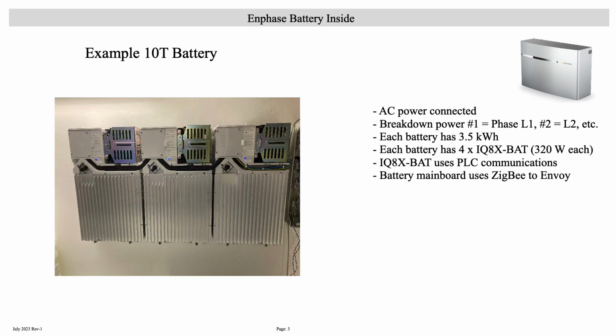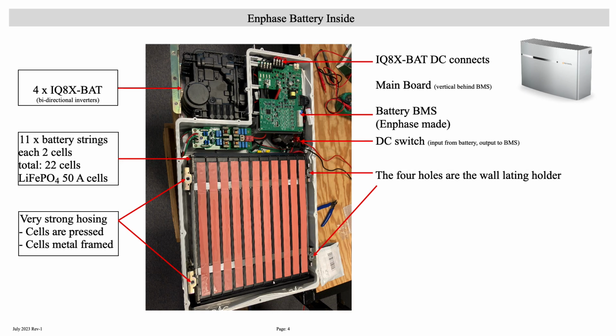On the front of the battery, we saw the back. There is a so-called DC switch, here, and it disconnects the entire battery from the electronics. This is very important in case of turning the battery offline. You need to turn this off, or when it's getting shipped, or if there's any kind of trouble, you need to turn the DC switch off.